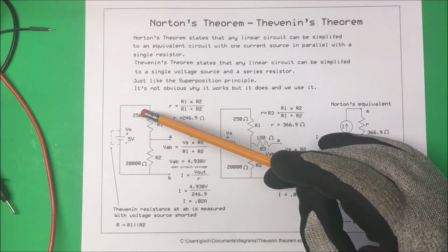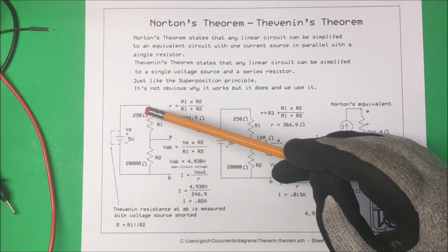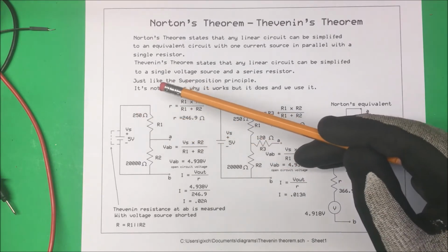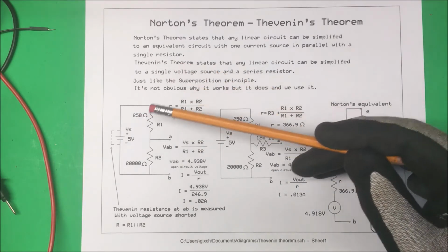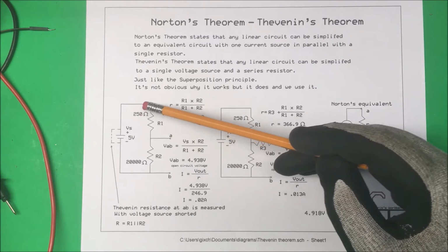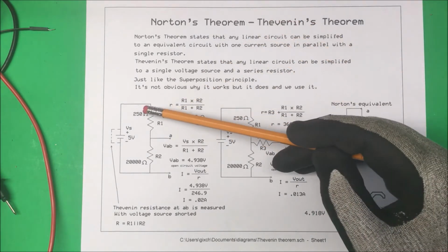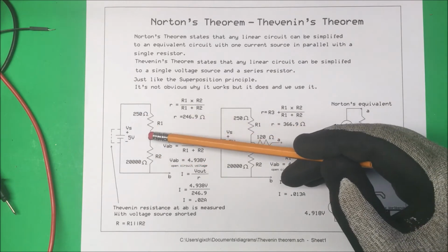Now, if you're doing this circuit, this 250 ohm resistor, they're not common. I use those because transmitters put out 4 to 20 milliamps, and 20 milliamps into 250 ohms gives me 5 volts, and 4 milliamps into 250 ohms gives me 1 volt. So it just makes it easier. So I have ordered these special. Anyway, you can use whatever resistor you have there.